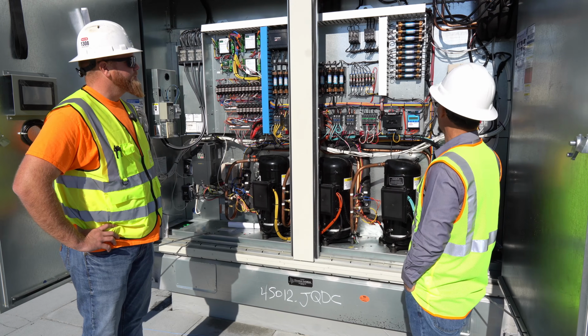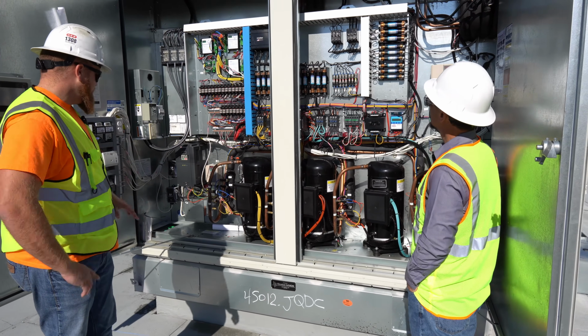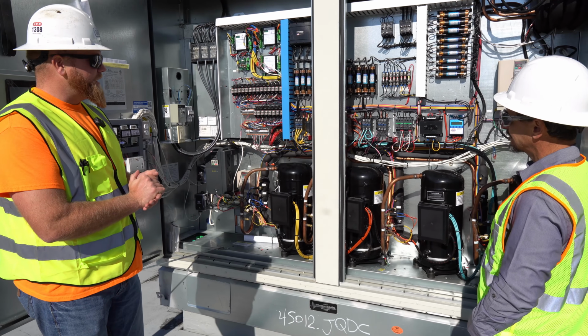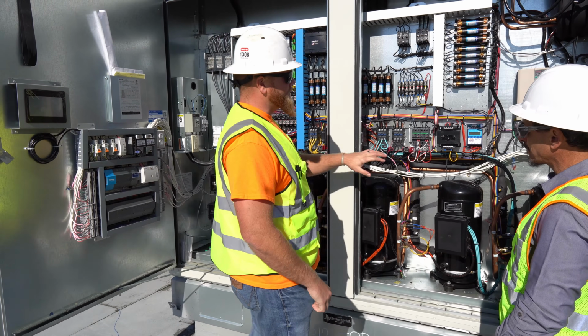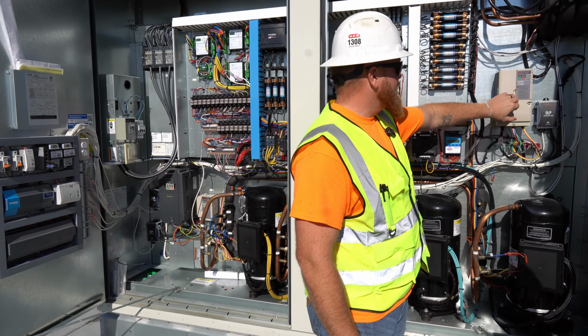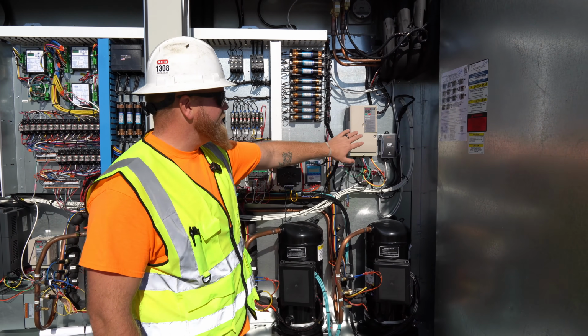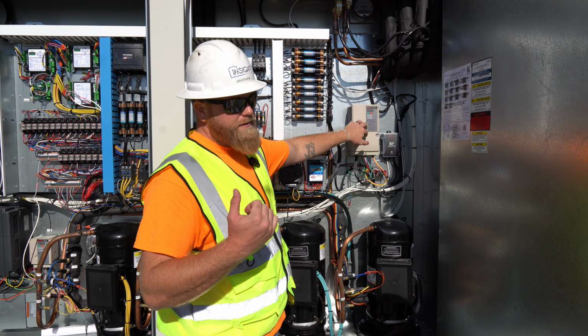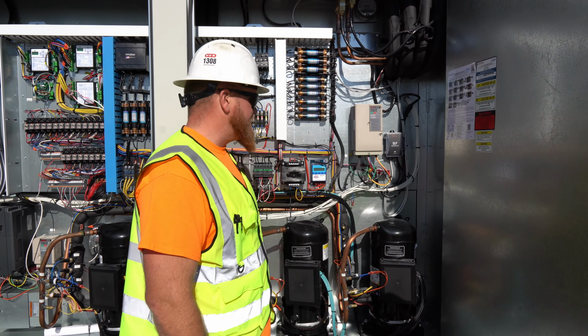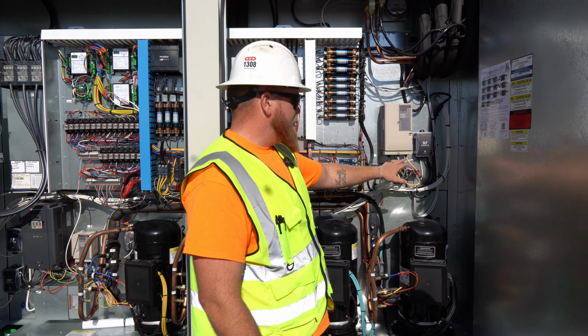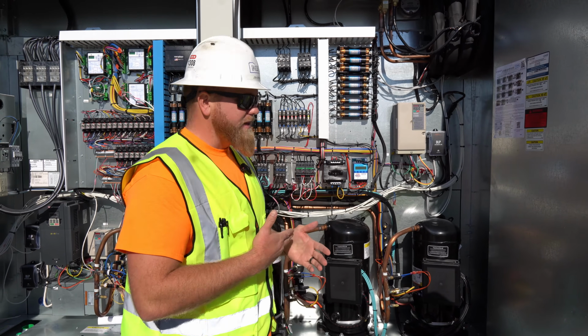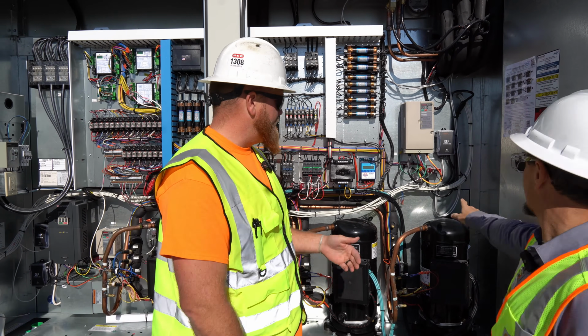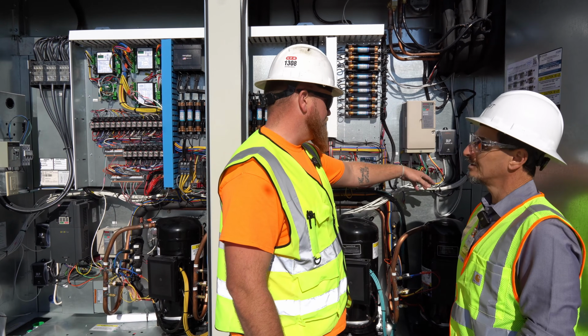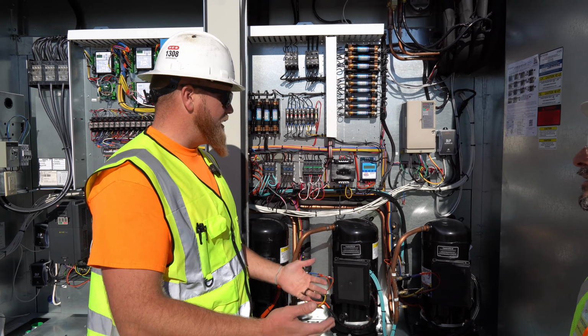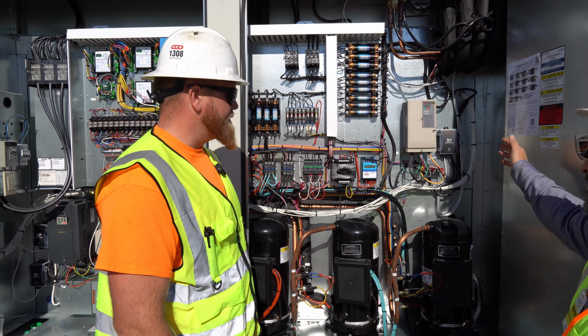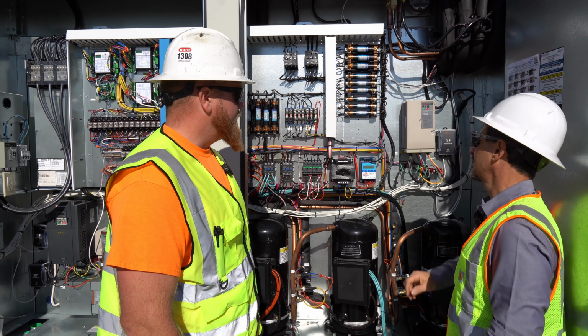So we have some CTs in here we're going to look at? Yeah, so the VFDs, every motor that we have in here is based on a VFD. Starting from right here, this is the supply fan VFD. This will be controlling the motor for the supply fan about the duct static, ramping up and ramping down. We do get motor feedback from these, so we can see a percentage demand of what the fan is actually putting out. And then that is a CT, so we can monitor the on and off power consumption of the feedback that comes through the drive, and this is just the power.